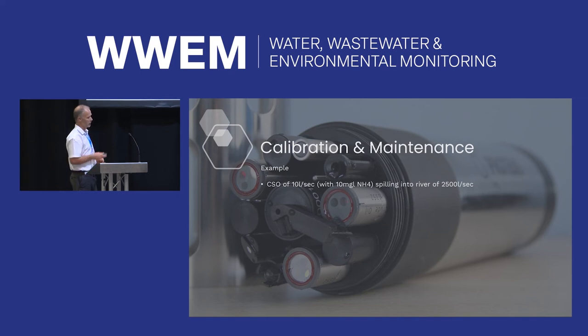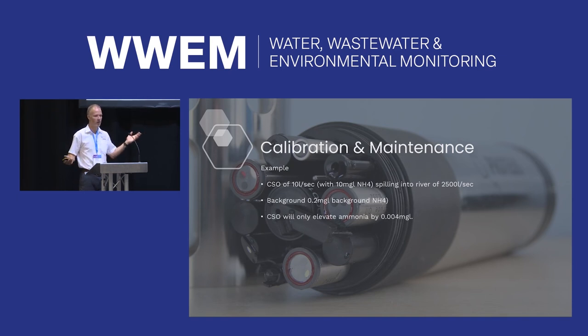So just going to give you an example, and this really can apply to any ammonia instrument. If you've got a CSO of 10 litres a second at 10 milligrams per litre, into a river of 2,500 litres a second, so that's probably a river 4 or 5 metres wide, something like that, with a background reading of 0.2.